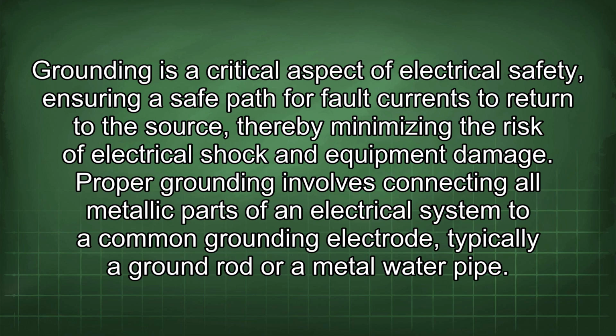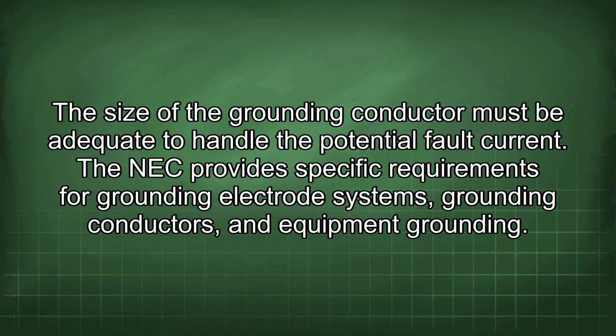Proper grounding involves connecting all metallic parts of an electrical system to a common grounding electrode, typically a ground rod or a metal water pipe. The size of the grounding conductor must be adequate to handle the potential fault current. The NEC provides specific requirements for grounding electrode systems, grounding conductors, and equipment grounding.